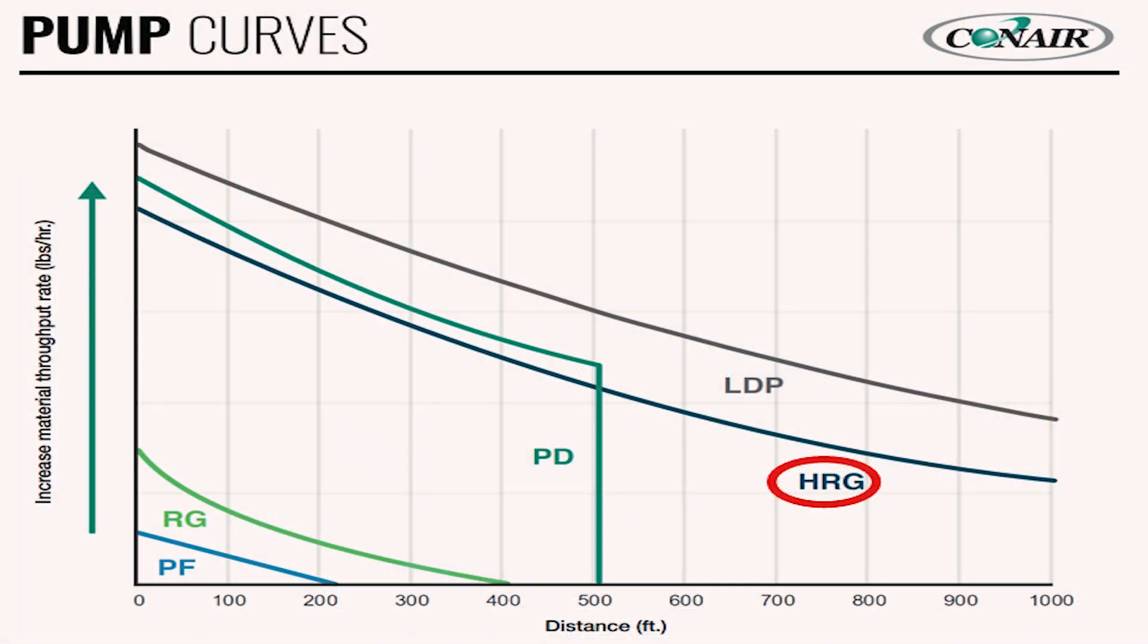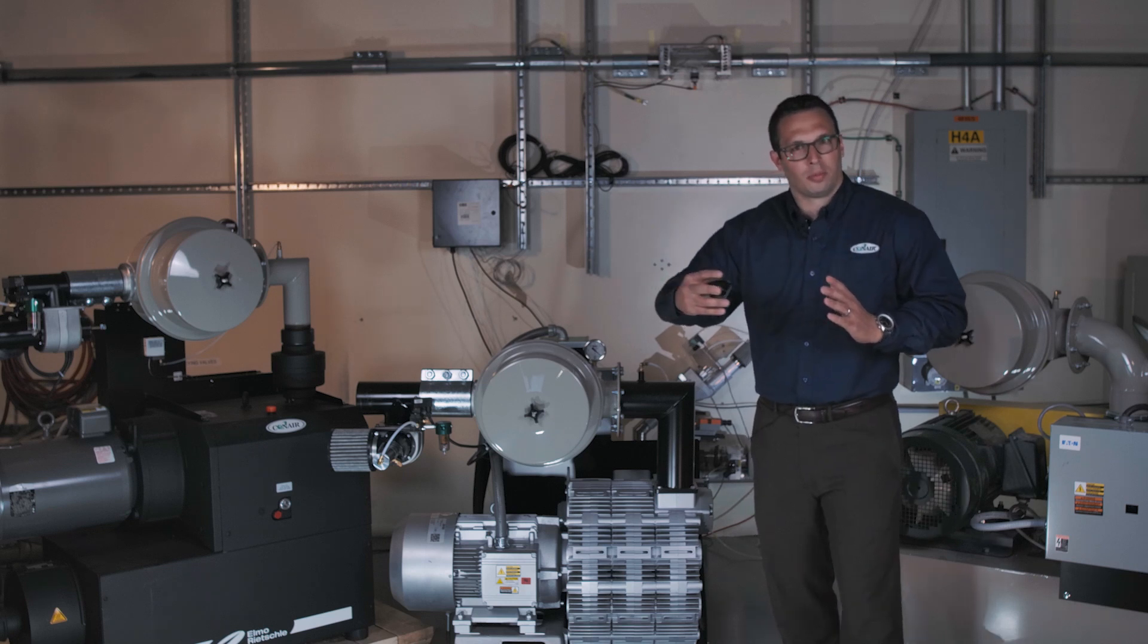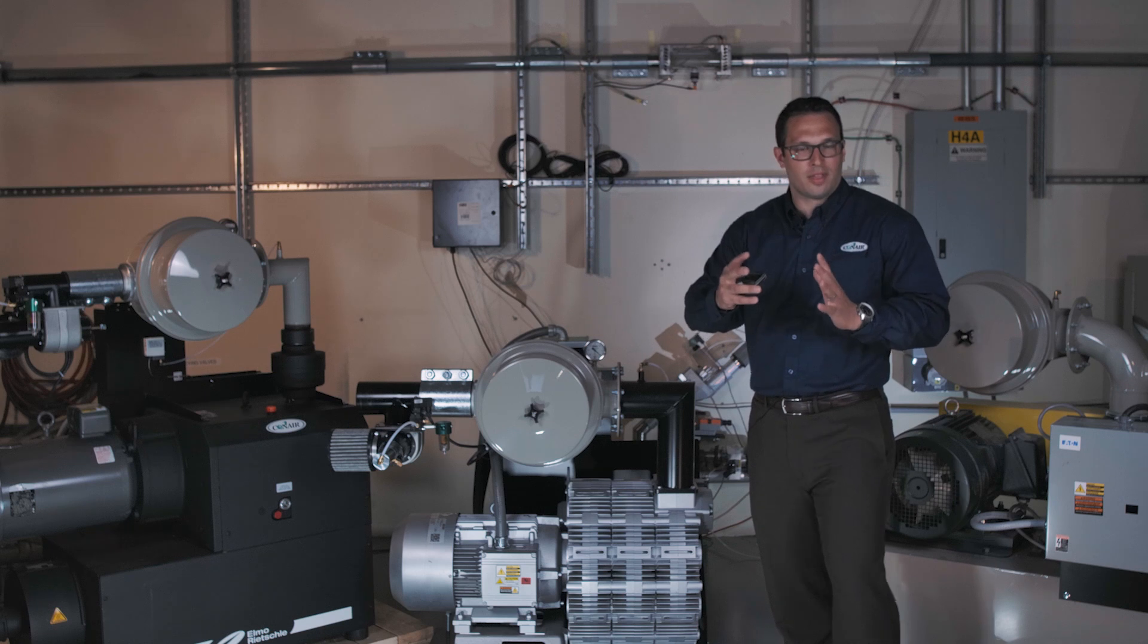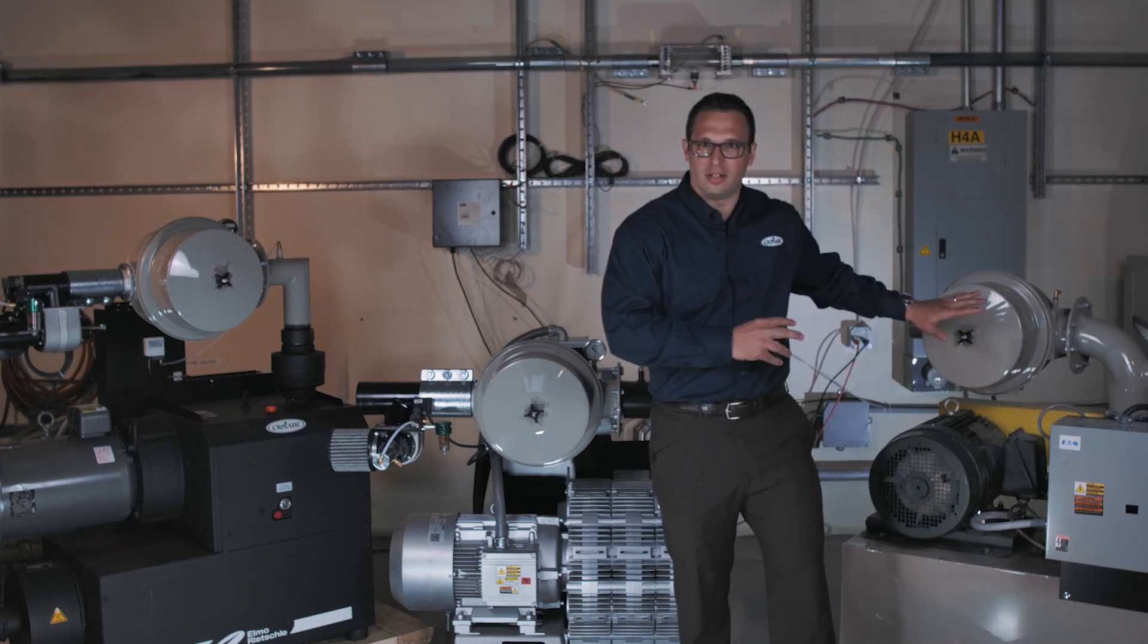As you can see on this pump comparison chart that we have here, I show PD, I show LDP, and I also show our new HRG pump, and see how the HRG pump now fits into this area where it's going to be for the longer distances. Again, the farther you convey, the more vacuum is required at that pump itself, the pump capability, to be able to keep that resin moving. Also notice on the throughput side of the curve, which will be the y-axis, the HRG and the positive displacement pumps almost mirror themselves. But then once that positive displacement pump runs out of vacuum capability, right at that 12 inches of mercury, we try not to go above that because the pumps themselves really are only capable of about 14 maximum.